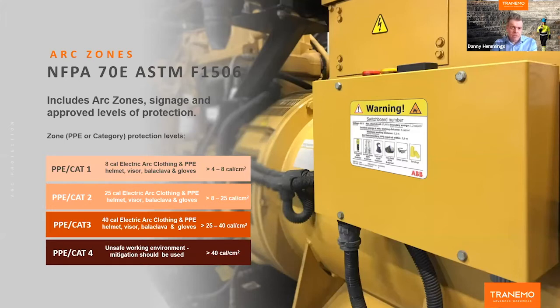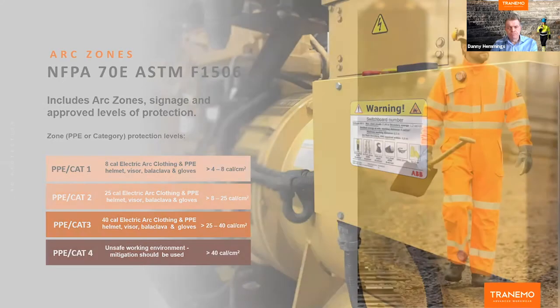And clearly there's a reason NFPA states that 40 cal should be the limit that's set. But 40 cal, it's a big incident, and it's quite a rare incident. And as I say, most of the time we will see users' requirements fit within category 2, PPE category 2, the 8 to 25 calorie range.